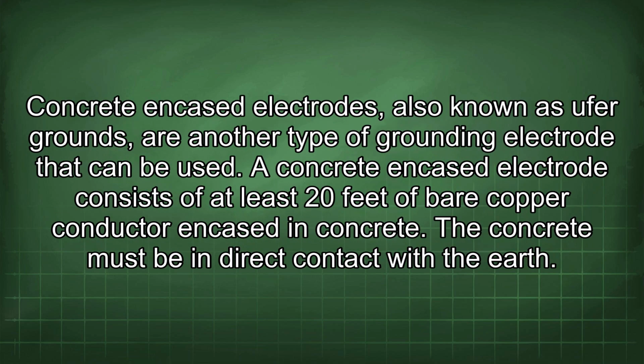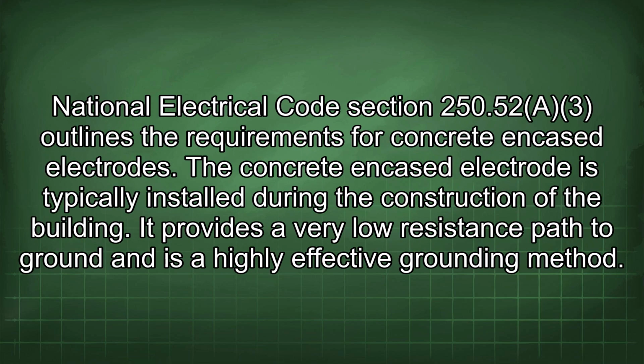Concrete encased electrodes, also known as Ufer grounds, are another type of grounding electrode that can be used. A concrete encased electrode consists of at least 20 feet of bare copper conductor encased in concrete. The concrete must be in direct contact with the earth. National Electrical Code Section 250.52(A)(3) outlines the requirements for concrete encased electrodes.